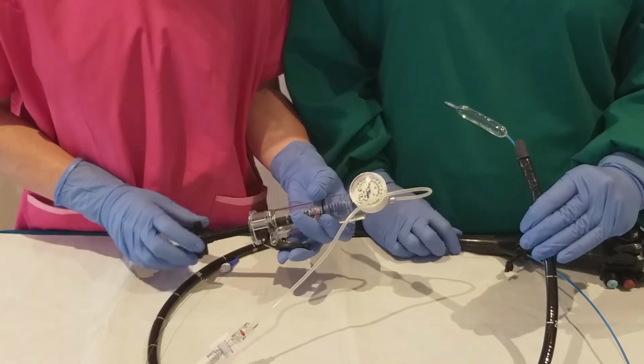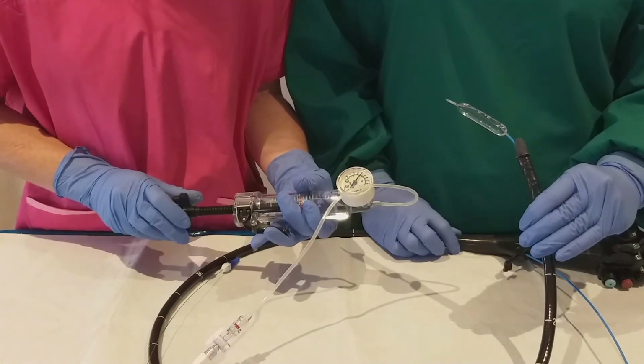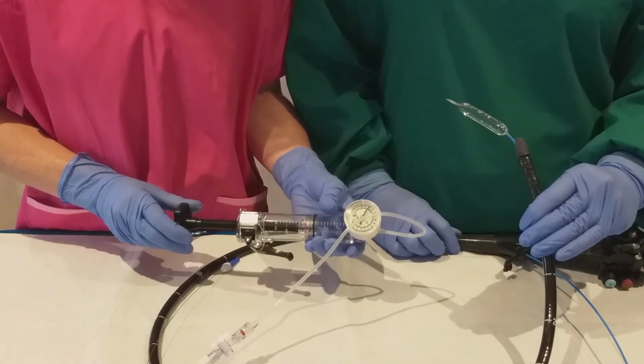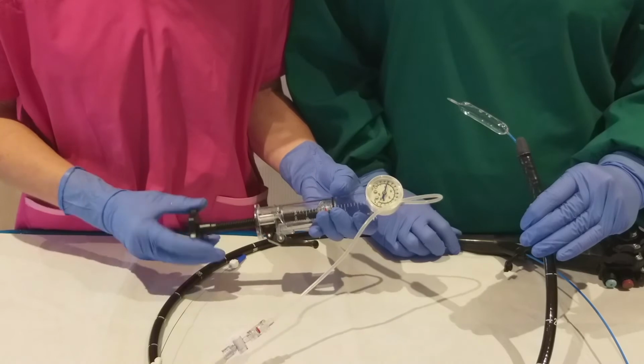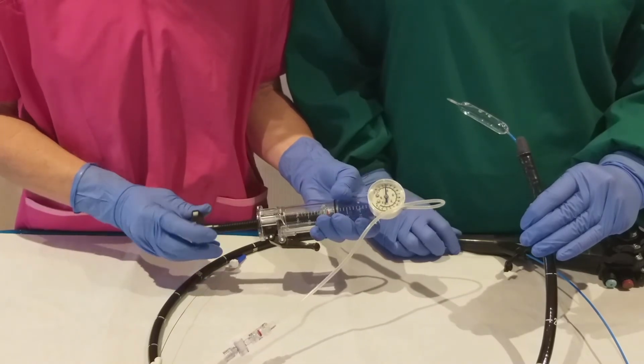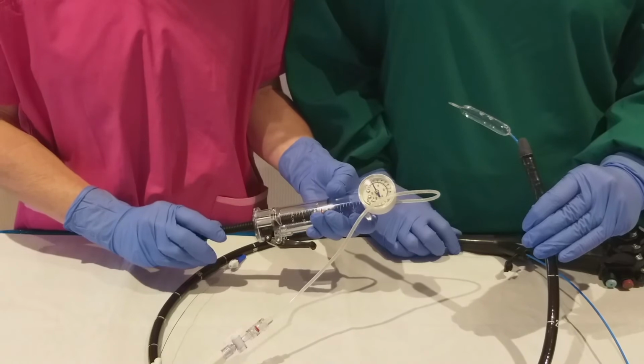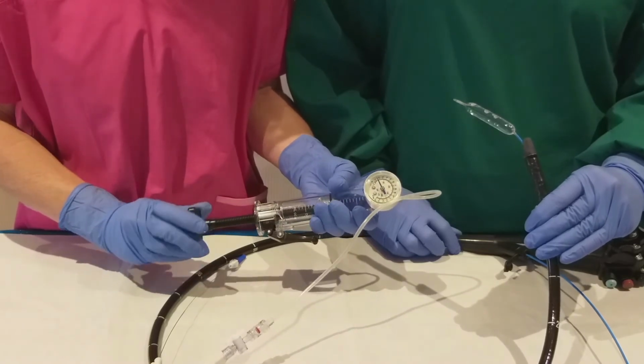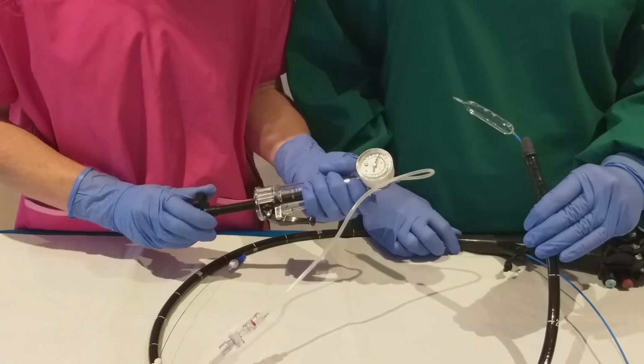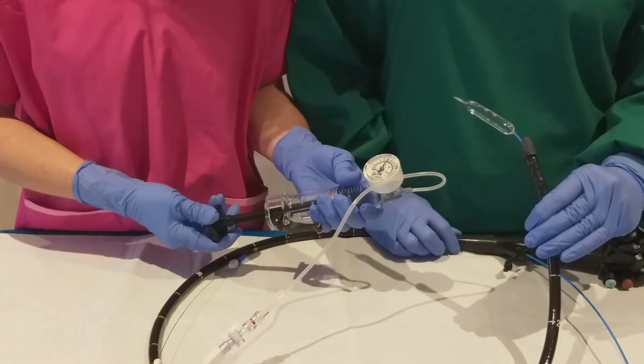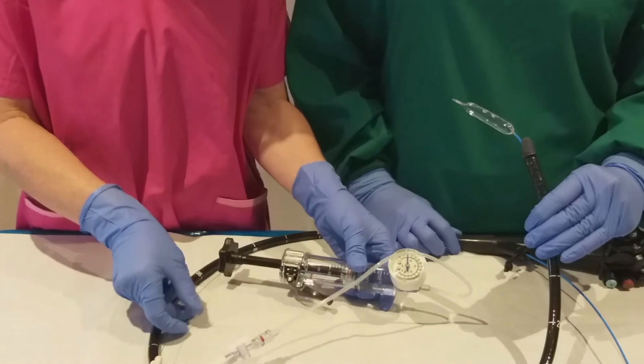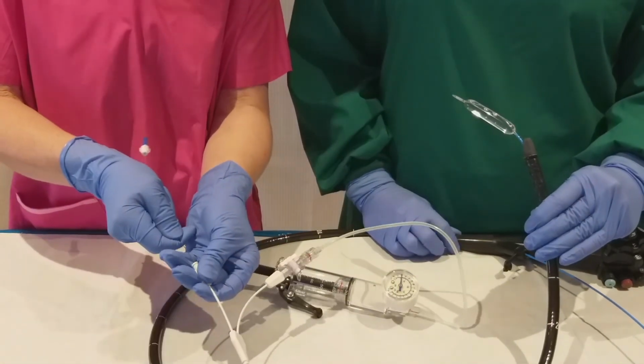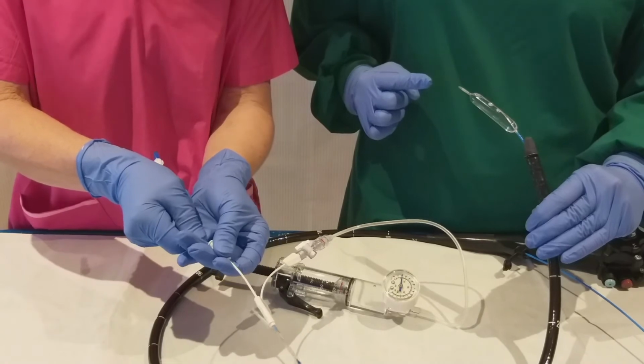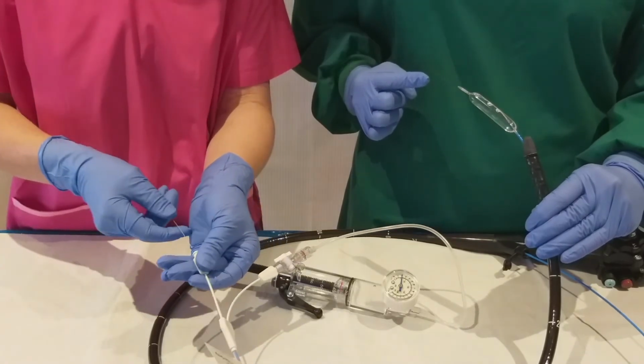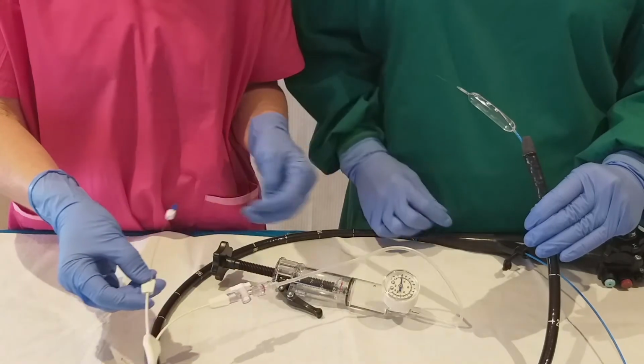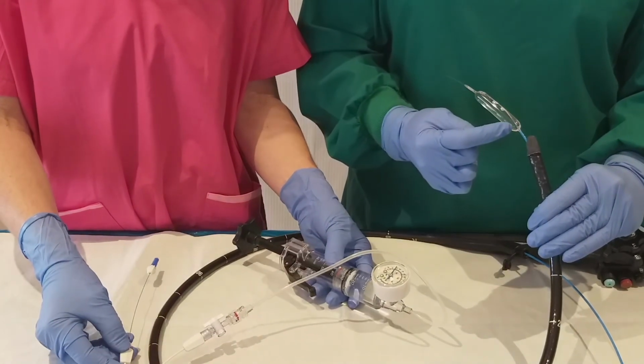It is normal to make minor adjustments as needed to maintain pressure. This is achieved by turning the inflation wheel clockwise. Alternatively, you may wind the wheel anti-clockwise to deflate the balloon to a smaller size. The balloon can be inflated and deflated as many times as required during the procedure. If required, the guide wire can be advanced to assist with other strictures during the procedure. The position of the balloon can be achieved or verified through fluoroscopy with the help of radiopaque markers.